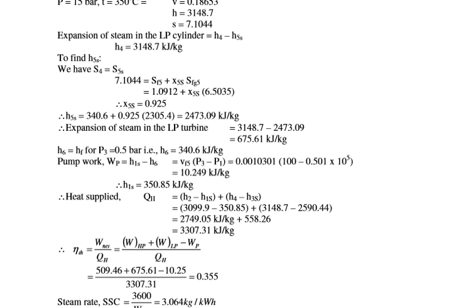From X5 = 0.925, calculate H5 = HF5 + X5 × HFG5 = 2473.09 kJ per kg. The expansion of steam in the LP turbine is H4 minus H5S = 3148.7 minus 2473.09 = 675.61 kJ per kg.